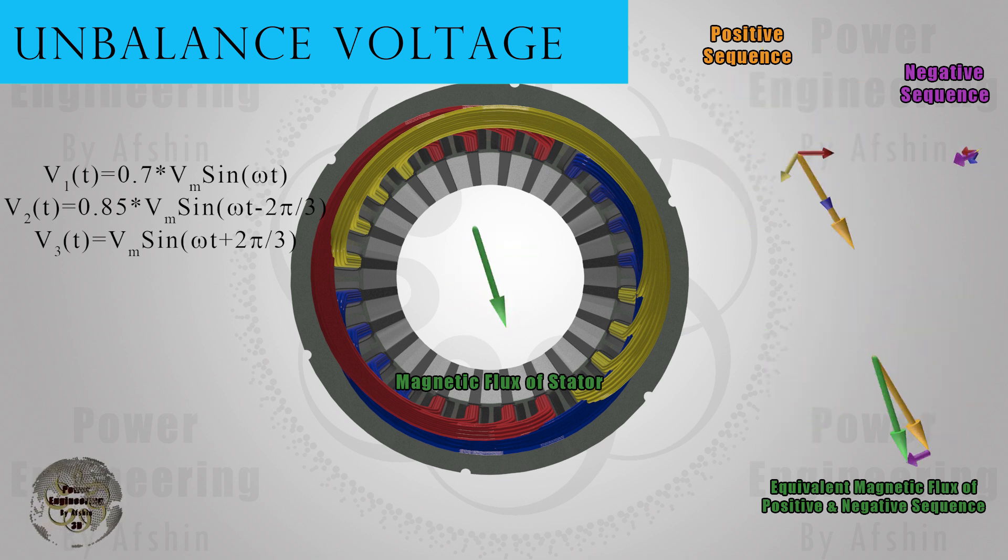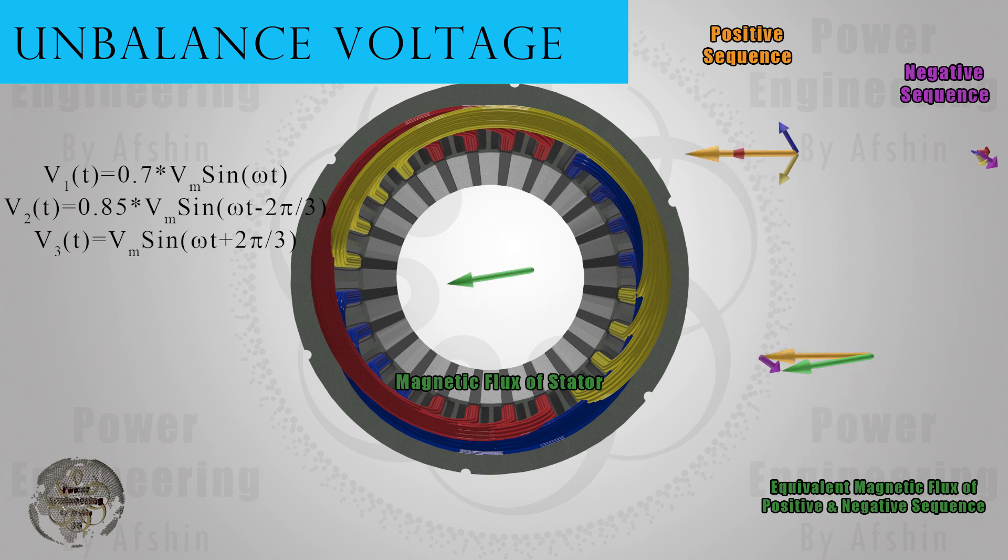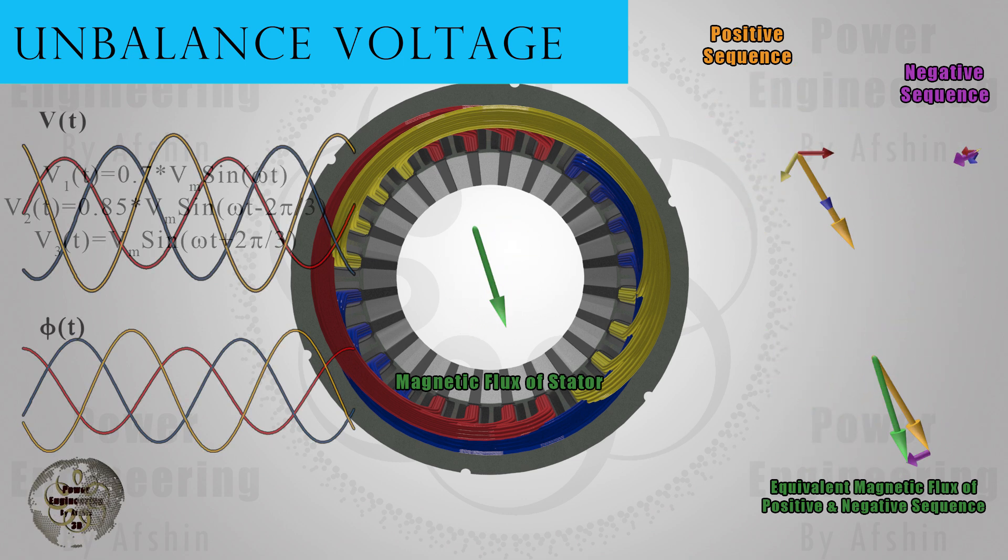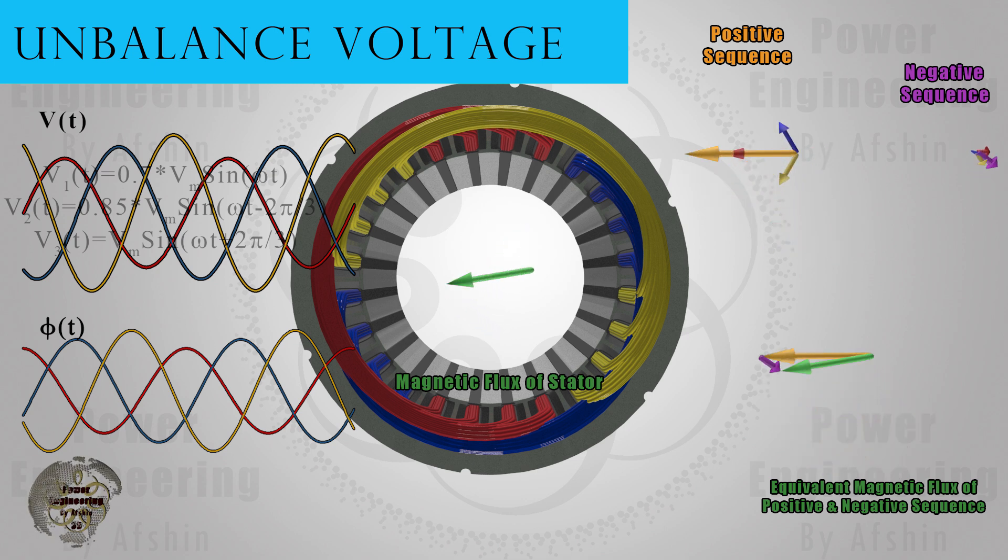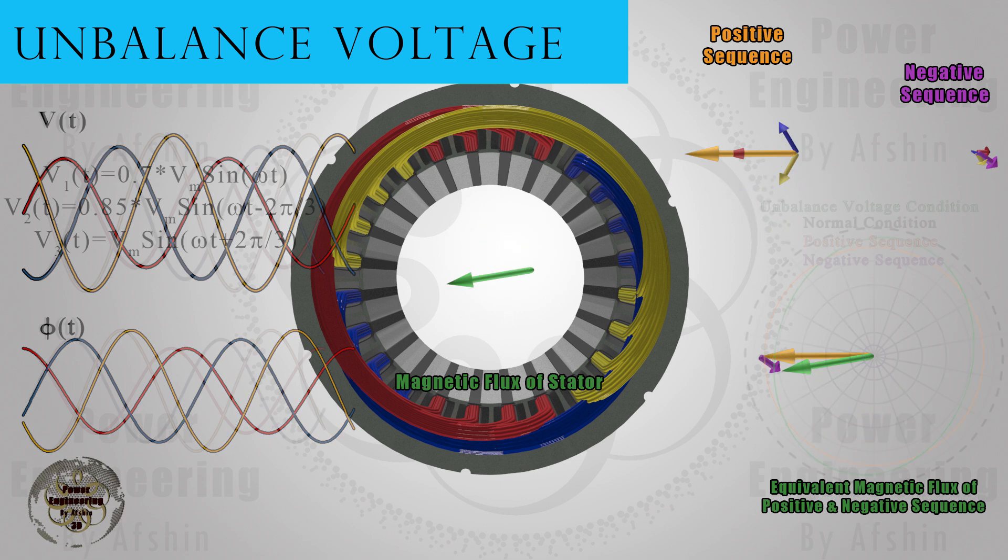As you can see on the left side, the voltage of the first phase has decreased by 30 percent, and the voltage of the second phase has decreased by 15 percent. With this voltage, the field inside the motor's surface is not uniform, and it changes based on the location of each phase winding. As observed, the field has taken an elliptical shape.